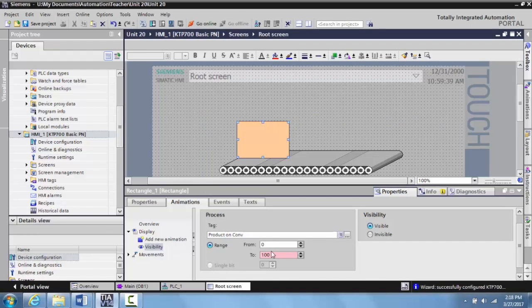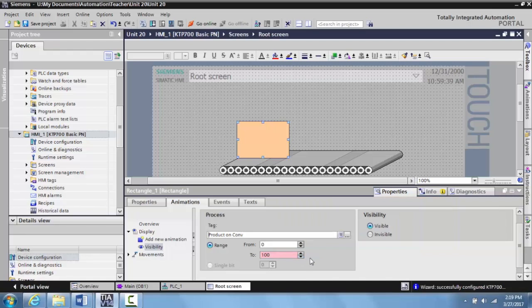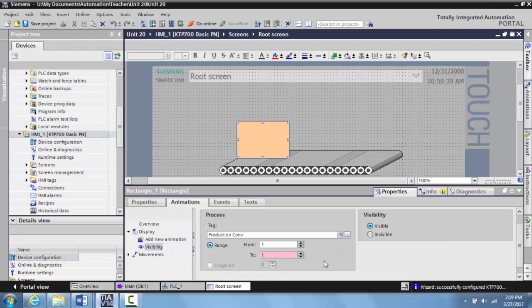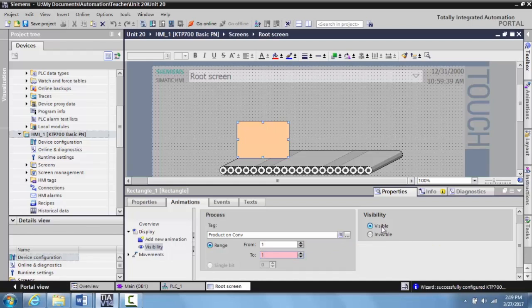Now as this is booting up, what we can do is we need to select its range. This is just a binary output, it's either on or it's off. But if I were using a counter or a timer, its accumulated value, I may want to change this around and make it only visible for five seconds or something like that. So what I want to do is I'm going to change this to one, and I'm going to change this to one as well. And when that value is one from one to one, so basically whenever it's on, it will be visible.